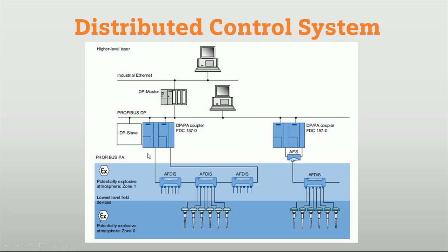The AFD-IS (active field distributor IS) is used for potentially explosive areas — here we have Zone 0 and Zone 1. Based on the zone, we select the appropriate field devices, all connected with the active field distributor. The AFD is connected in a ring configuration so that when any communication link fails, the AFD can carry information via the second link to the automation station. The AFS active field splitter is used for making redundancy with the coupler, so when a coupler fails, data can be sent to the automation station or DP master via the second direction.